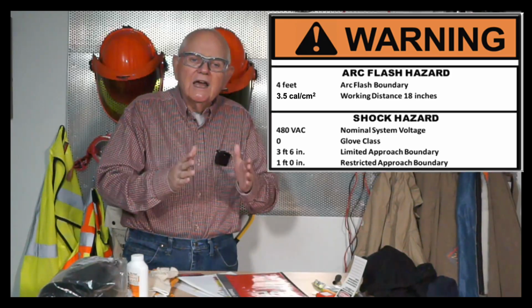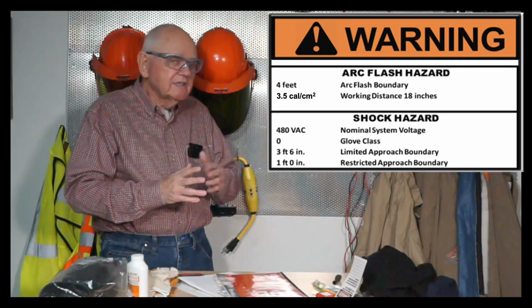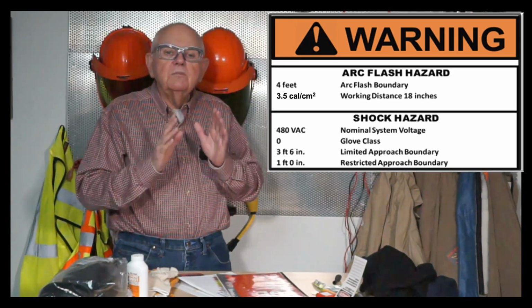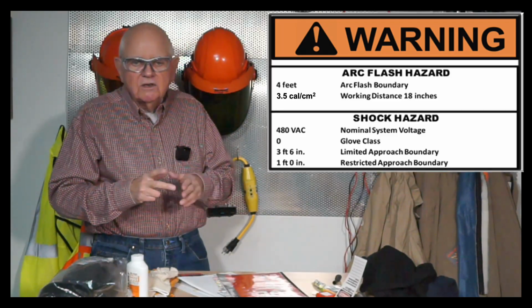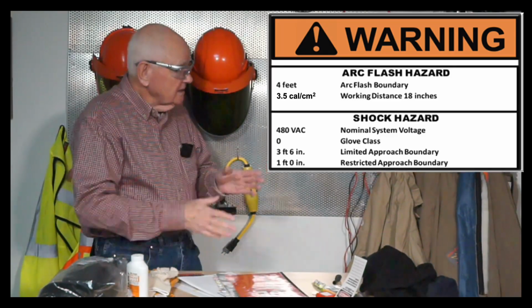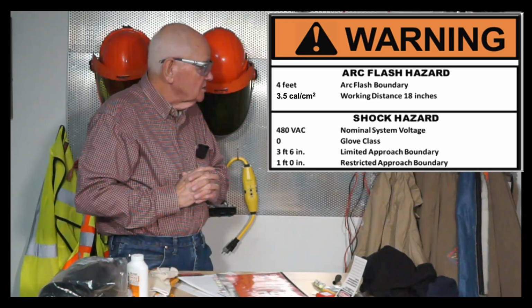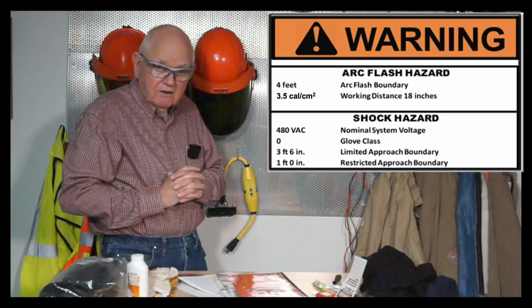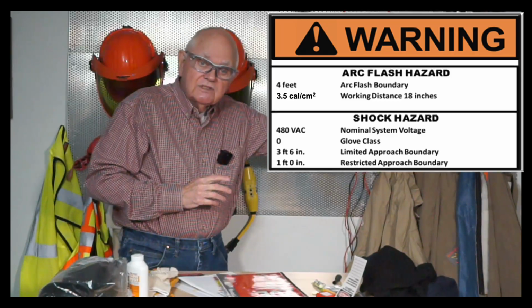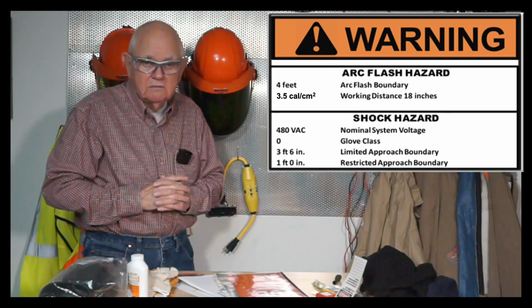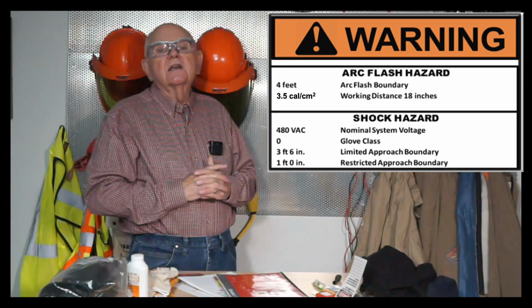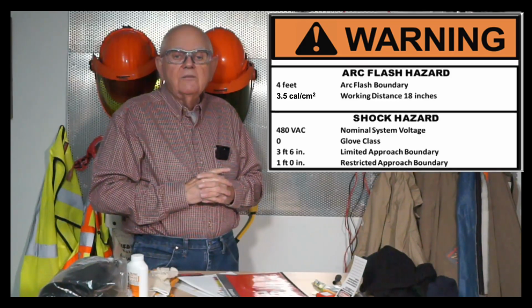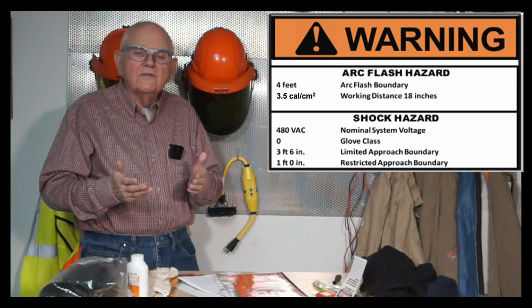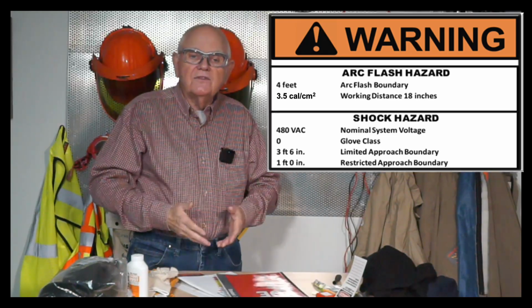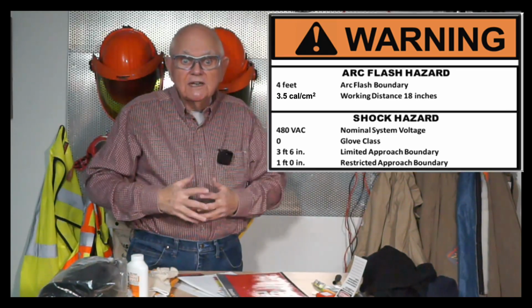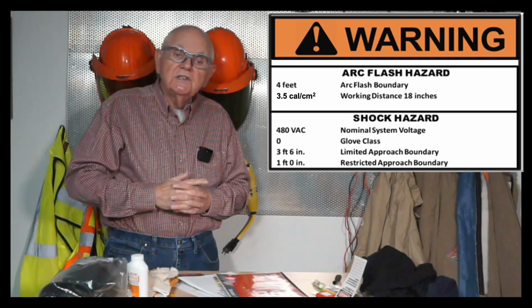One of the problems that I constantly see with labeling, people will take this label and they will also put the PPE category on it. So it'll say, for instance, this particular label says I have 3.5 calories at 18 inches of working distance. 3.5 calories. Then I go over here and maybe somewhere else I put PPE category 1. That can create confusion, and that's not allowed by NFPA 70E. I'm not allowed to use both the PPE category method and the incident energy analysis method to warn people how to protect themselves out there in the field. And the reason is the confusion.